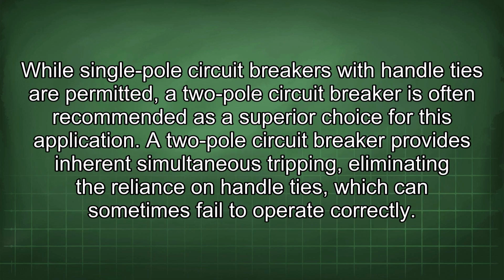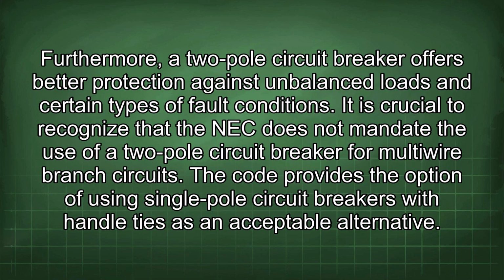While single-pole circuit breakers with handle ties are permitted, a two-pole circuit breaker is often recommended as a superior choice for this application. The two-pole circuit breaker provides inherent simultaneous tripping, eliminating the reliance on handle ties, which can sometimes fail to operate correctly. Furthermore, a two-pole circuit breaker offers better protection against imbalanced loads and certain types of fault conditions.